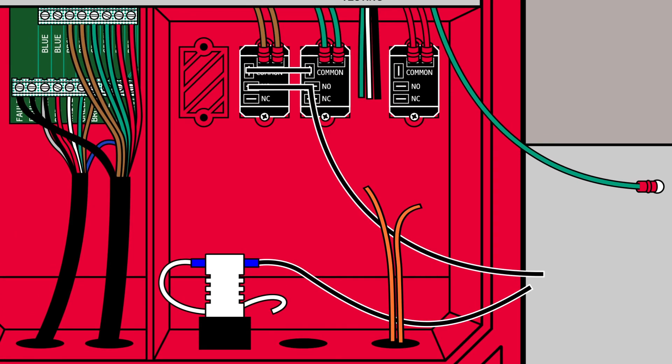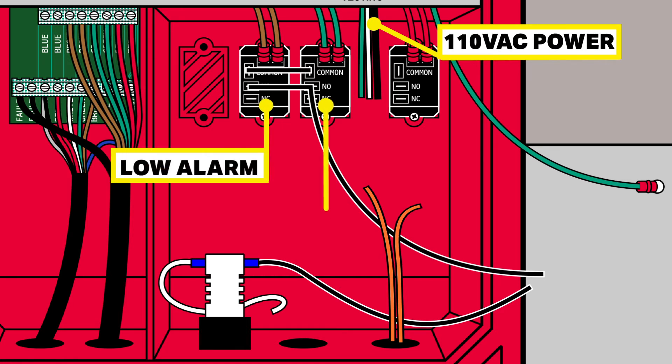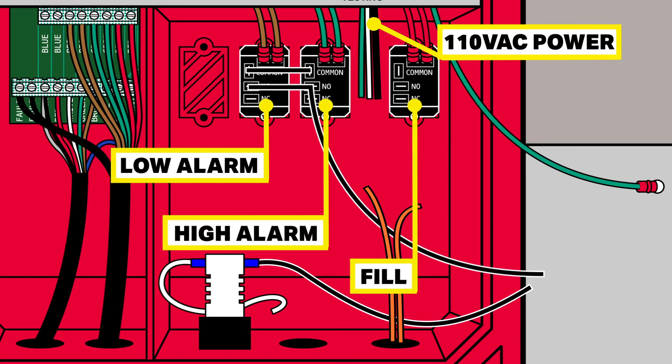In the high-voltage area, there are three power wires for the power-in connections: black, white, and green. There are also three relays for low alarm, high alarm, and fill, each with colored wire for the respective sensor rod.